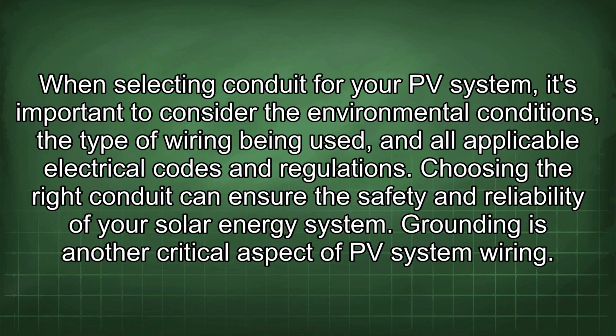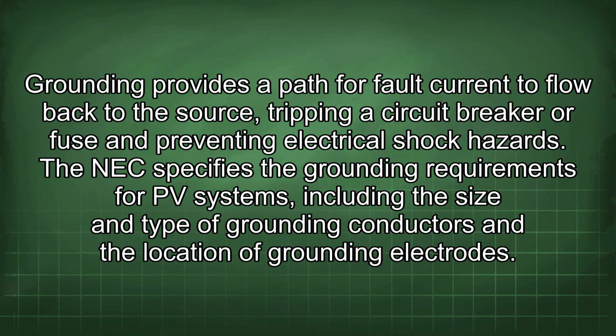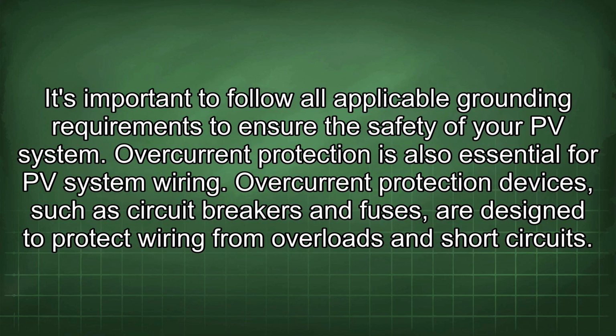Grounding is another critical aspect of PV system wiring. Grounding provides a path for fault current to flow back to the source, tripping a circuit breaker or fuse and preventing electrical shock hazards. The NEC specifies the grounding requirements for PV systems, including the size and type of grounding conductors and the location of grounding electrodes. It's important to follow all applicable grounding requirements to ensure the safety of your PV system.